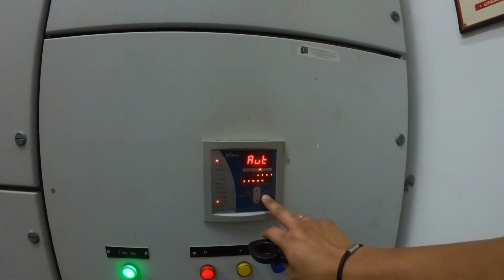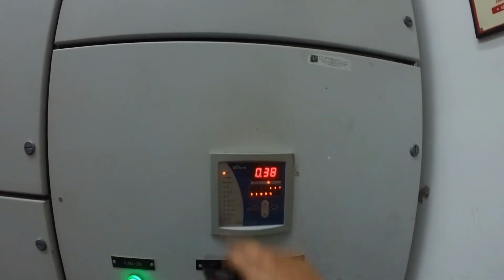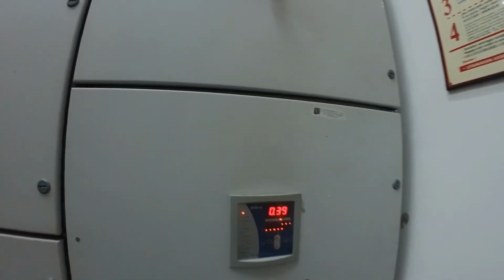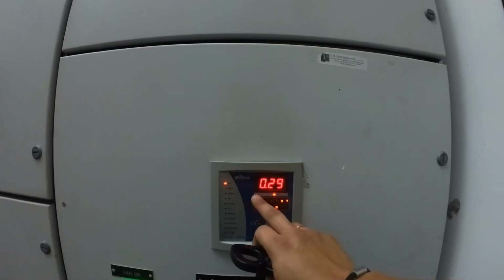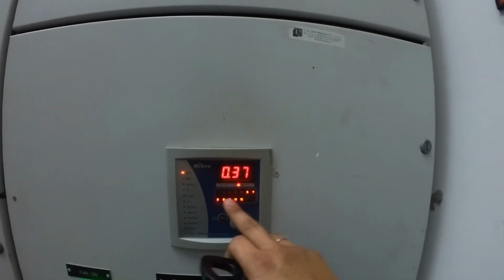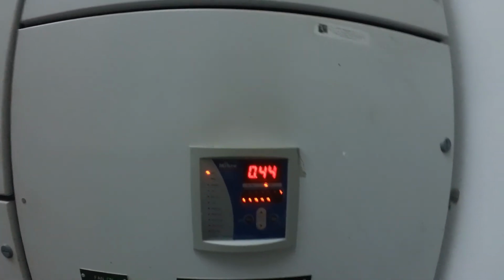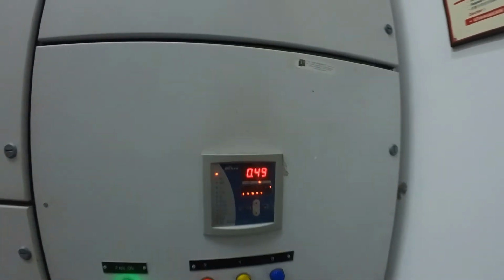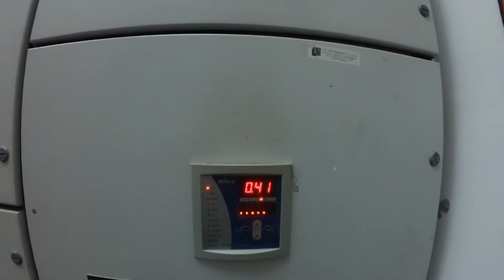As you shift it back, the power factor value is now overcompensated, so that's why it's on the capacitive side. As the steps switch off one by one, this value will go back to the target power factor value, which is 1.00.